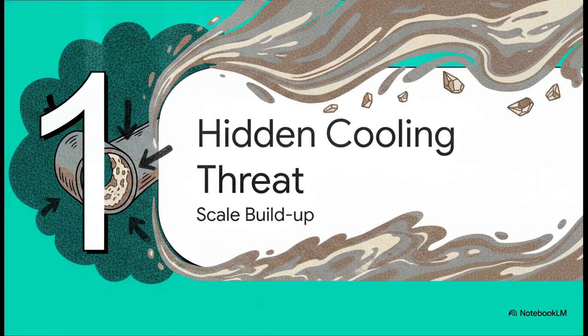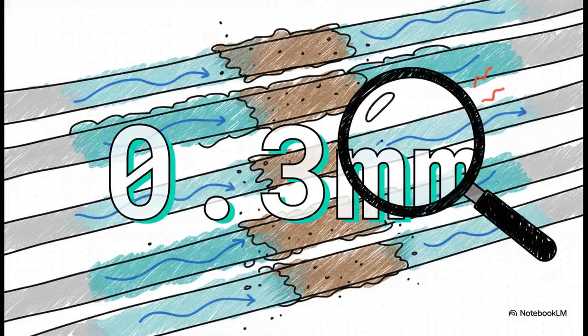To really appreciate the hero here, we first have to understand the microscopic villain it's fighting. So, in a water-cooled system, the cooling water is constantly dragging in microscopic dust, impurities, and minerals like calcium and magnesium. Over time, these stick to the tubes, creating a buildup that facility managers call scale. And what's wild here is just how little of this stuff it takes to cause absolute havoc. We're talking about a mere 0.3 millimeters. That is a tiny fraction of a millimeter thick, but it acts like this unwanted thermal blanket, trapping heat and stopping the tubes from effectively cooling the water.